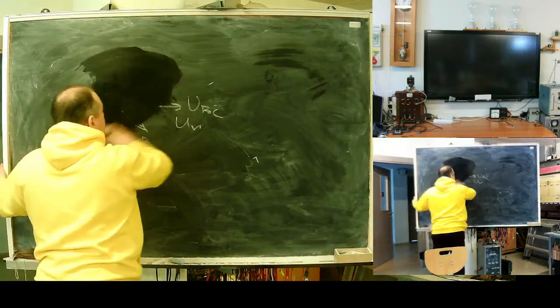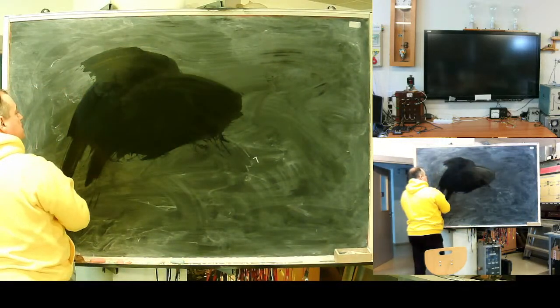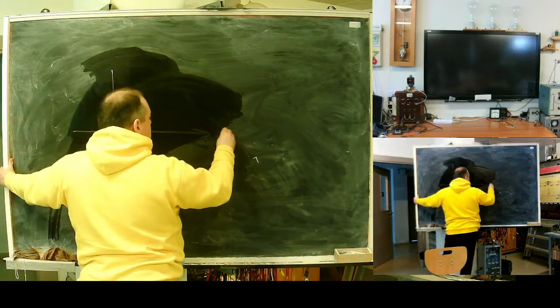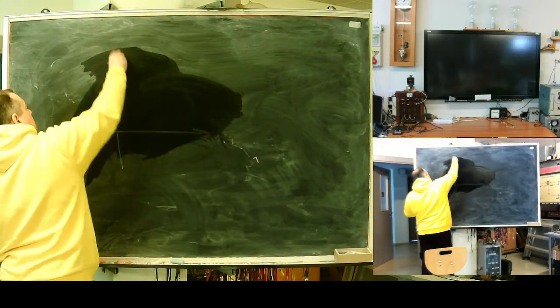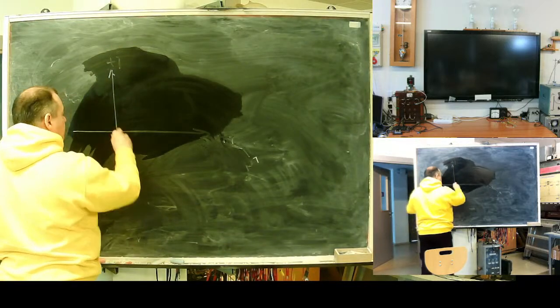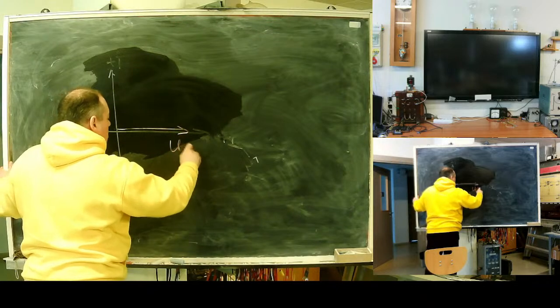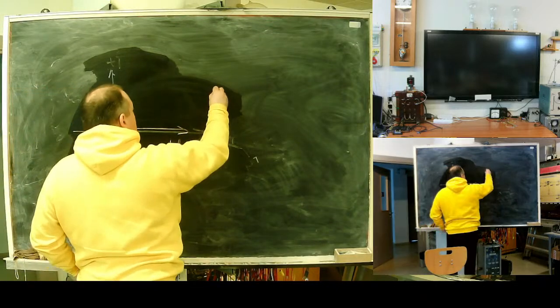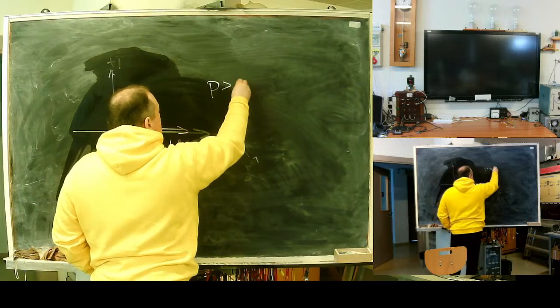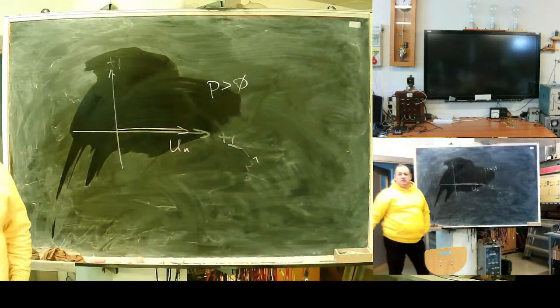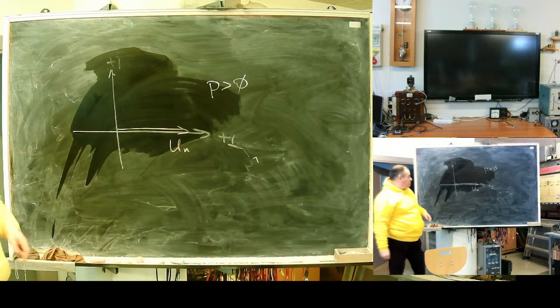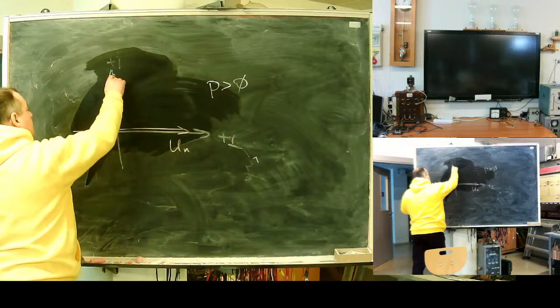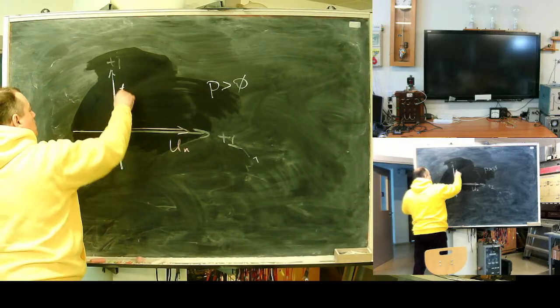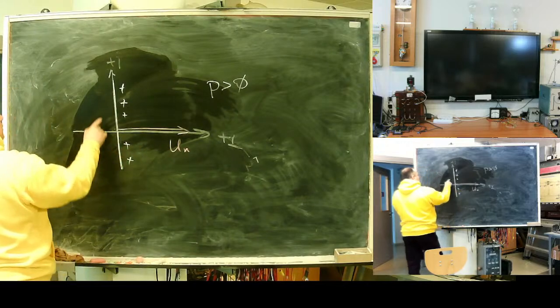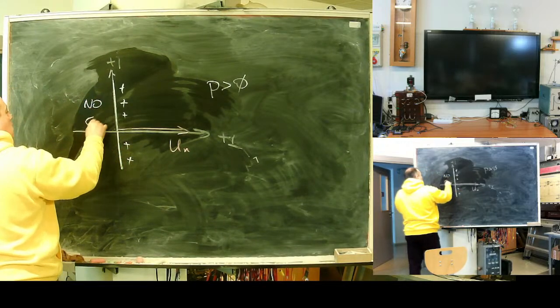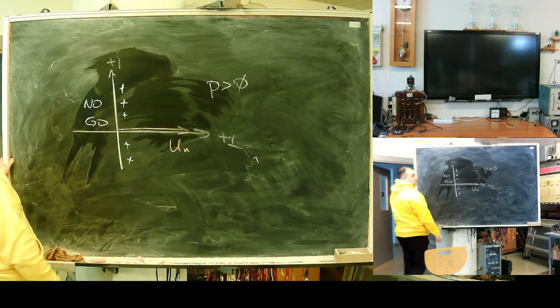Very simple analysis. What will be the characteristic for the meter? For voltage of relay, if my trip characteristic is simple, P greater than 0, what kind of characteristic will I have? Operate, operate, operate. No operate. Understood?